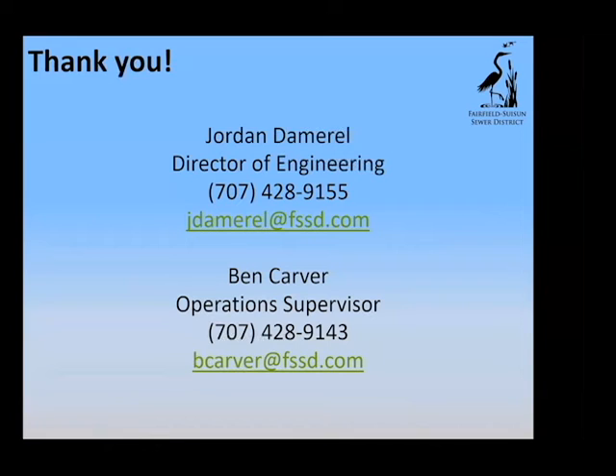Did you consider APG's dual core blowers to save even more space? Yes, we did consider that. Neuros makes a dual core blower, which is essentially two of the cores Ben showed you in the upper section combined in the same package. It simplifies installation, giving you one blower box with basically double the air capacity. We did look at those, but had some concern about the reliability of having a single VFD and a single cooling system. If there's an issue with one of those common components, you could lose half your air capacity rather than 25%. So we did consider it, but opted to stick with the single core to increase reliability.